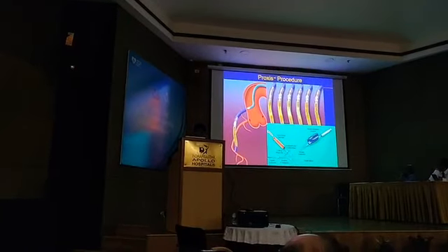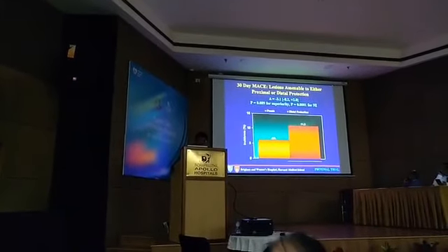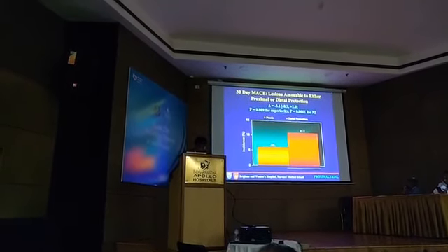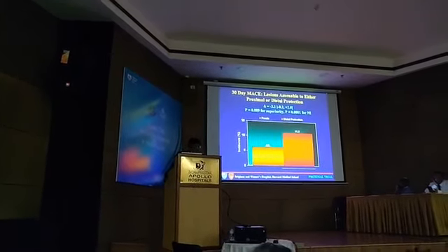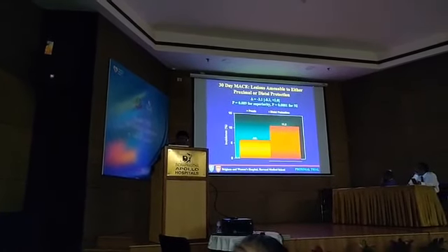Then comes the proximal occlusion. Occlude the proximal segment, this is how the concept is. And then perform the angioplasty through that, so that when you have inflated, there is no blood flow, and then you perform the procedure. A few trials have shown the comparison between the distal and proximal protection devices, and the proximal devices have fared better as compared to distal protection devices.